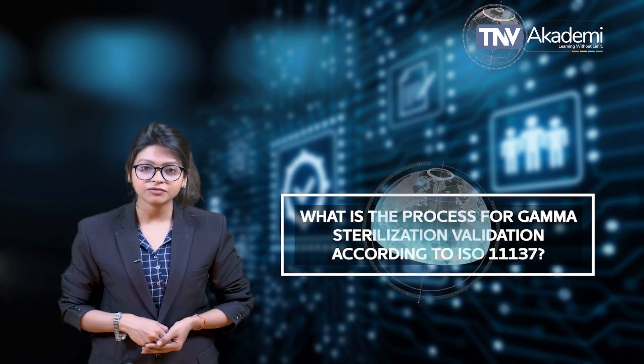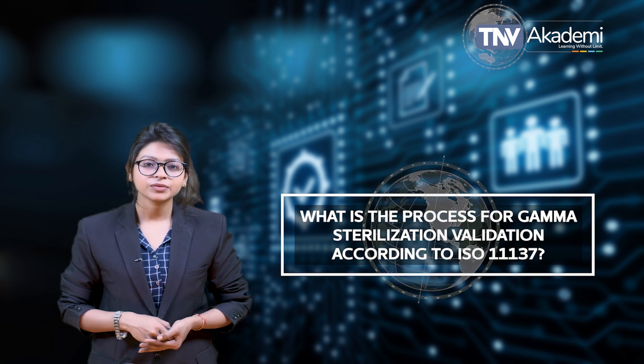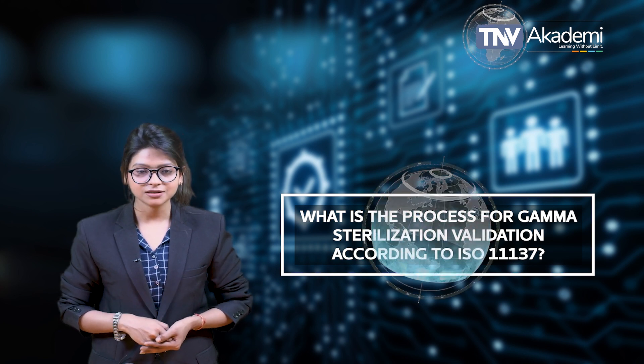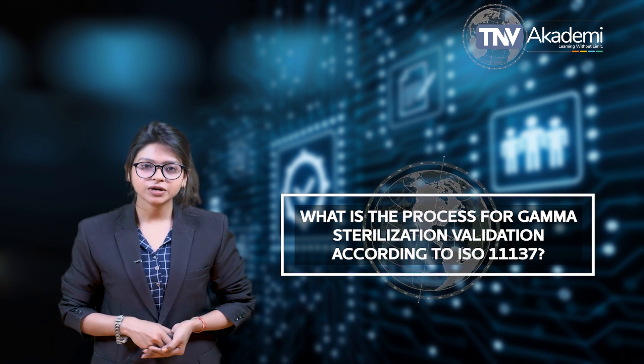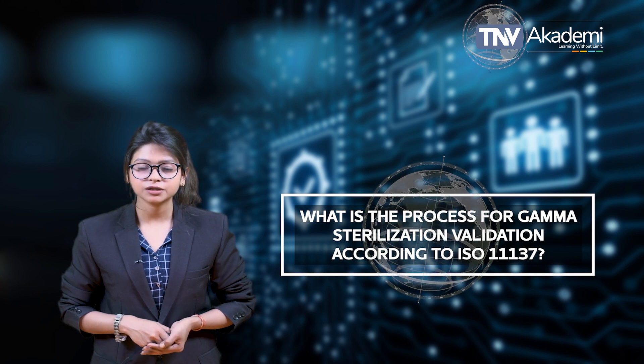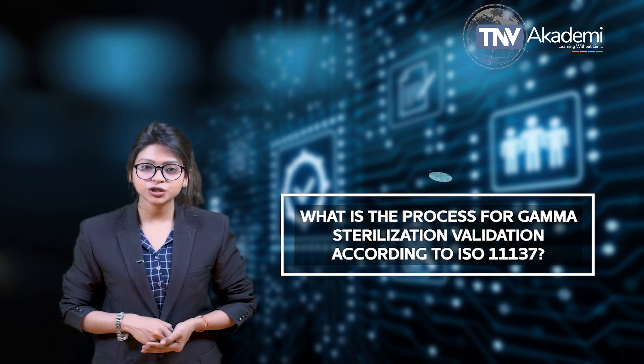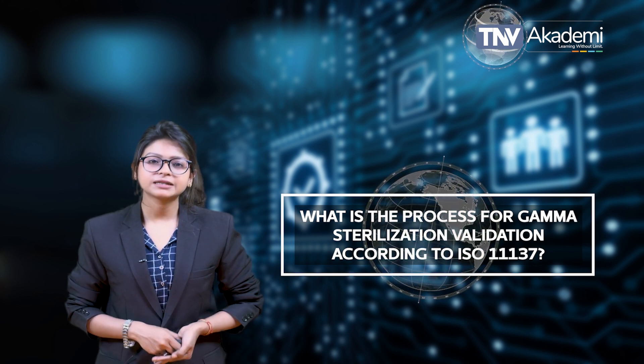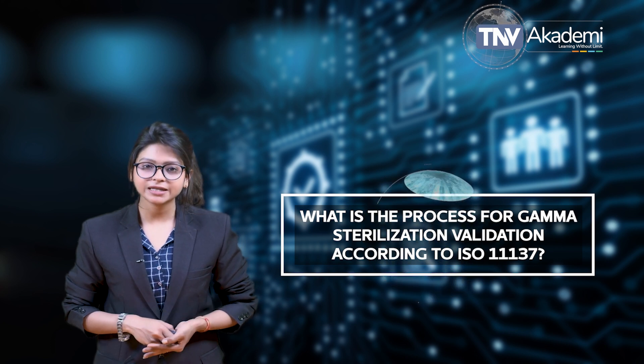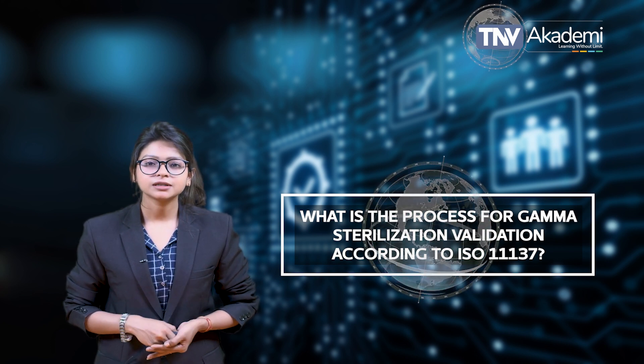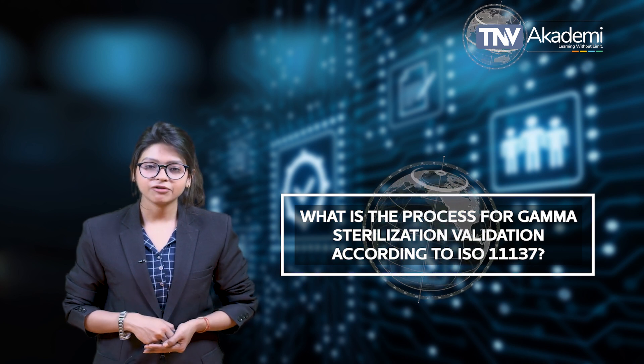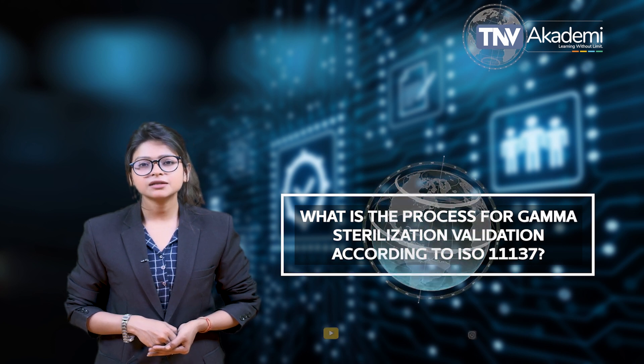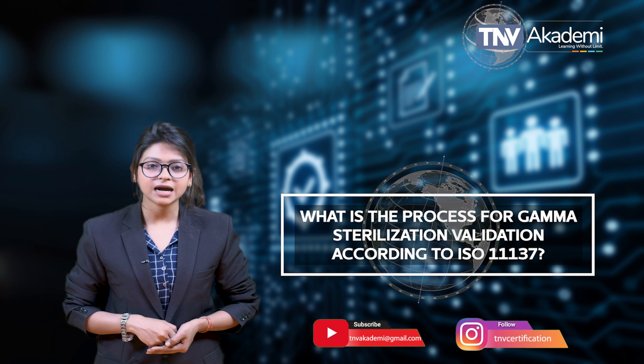A maximum dose must be established and not exceeded during gamma sterilization because gamma rays have the potential to break down the polymers used in many single-use medical devices that require sterilization. ISO 11137-2 offers three related methods for establishing a radiation dose that meets both requirements. The first two methods involve determining the natural bioburden — the number of microorganisms on a product — and verifying the appropriate dose via sterility testing.